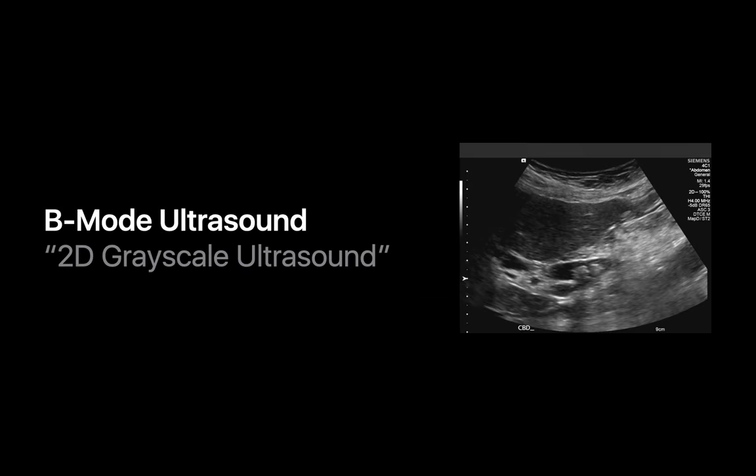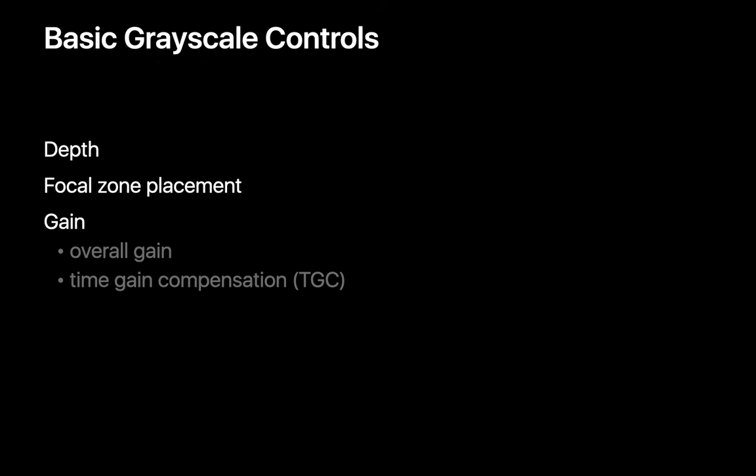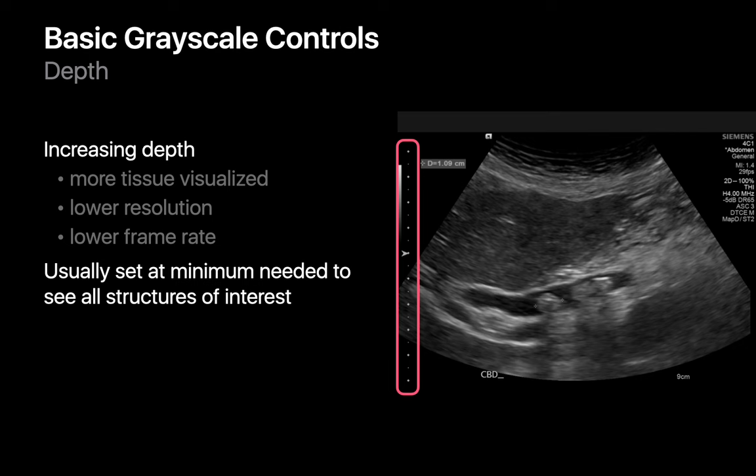When performing a 2D grayscale ultrasound study, there are three parameters you need to control: depth, focal zone placement, and gain. The depth of an ultrasound image is adjustable but requires balancing costs and benefits. Increasing image depth allows you to visualize more tissue, but comes with an image resolution and frame rate penalty. Therefore, depth is usually set to the minimum needed. Image depth is displayed as vertical gradations along either side of the image, usually with half-centimeter marks.